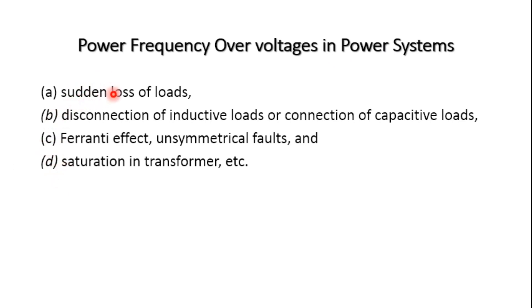The first condition is sudden loss of loads. Second is disconnection of inductive loads or connection of capacitive loads. Third is the Ferranti effect, where the receiving end voltage is greater than the sending end voltage because the transmission line behaves like a capacitance. Fourth is unsymmetrical faults — line to ground, line to line, double line to ground — and saturation in the transformers.